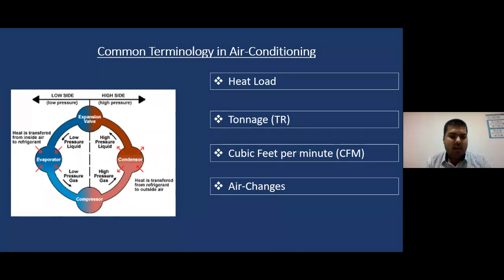Supply and return air. Supply is the air which is delivered from the evaporator to the room. But how would a compressor know that the temperature has been attained in my room? It should have some sensor. So if I set the temperature to 24 degrees Celsius, the conditioned air must reach the machine back at the same temperature so that it senses and switches off the compressor. So a basic cycle of supply and return air must go on. That is why most of the time you might have observed that the air conditioning guy asks you to keep a gap of 8 inches between the false ceiling and the split AC. Basically, that is the point where the sensor is kept so that the cycle of supply and return goes on.